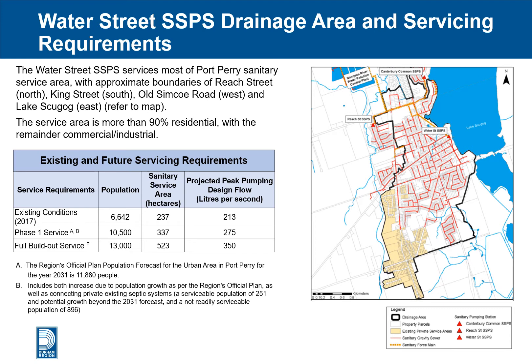The increase in pumping station capacity will happen in two stages. In the first stage, capacity will be provided for a population of 10,500, and in the future, pumping capacity will be expanded for a build-out population of 13,000. This phase one estimate is based on population growth in the region's official plan and includes existing populations now serviced by private septic systems that could be connected to the sanitary sewer collection system. The full build-out capacity services 523 hectares of sanitary service area with a 350 litre per second peak design flow.